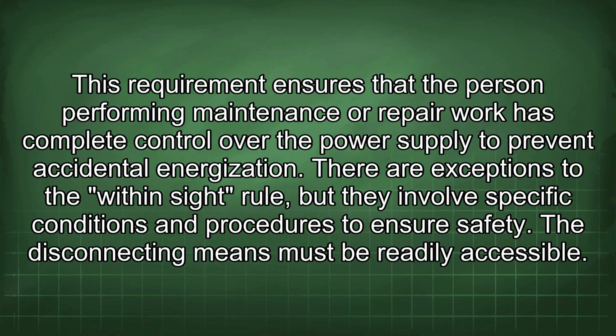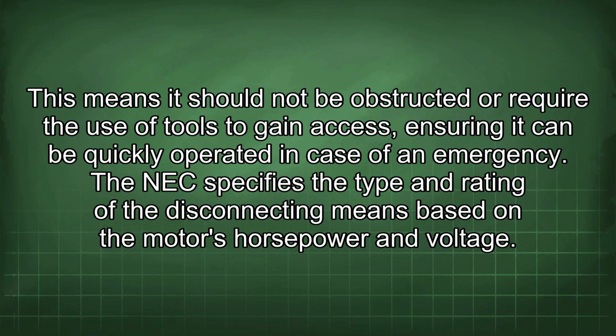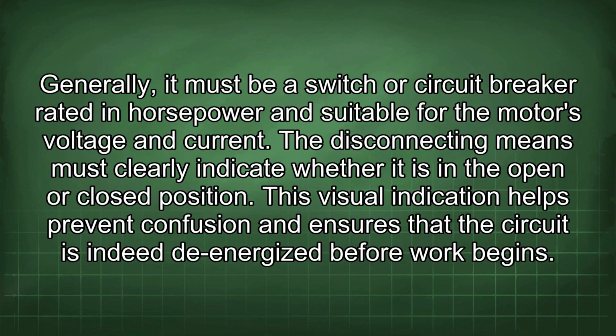The disconnecting means must be readily accessible. This means it should not be obstructed or require the use of tools to gain access, ensuring it can be quickly operated in case of an emergency. The NEC specifies the type and rating of the disconnecting means based on the motor's horsepower and voltage. Generally, it must be a switch or circuit breaker rated in horsepower and suitable for the motor's voltage and current. The disconnecting means must clearly indicate whether it is in the open or closed position. This visual indication helps prevent confusion and ensures that the circuit is indeed de-energized before work begins.